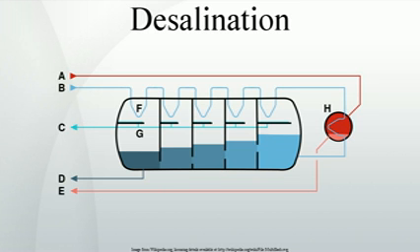Methods. The traditional process used in these operations is vacuum distillation, essentially the boiling of water at less than atmospheric pressure and thus a much lower temperature than normal. This is because the boiling of a liquid occurs when the vapor pressure equals the ambient pressure and vapor pressure increases with temperature. Thus, because of the reduced temperature, low-temperature waste heat from electrical power generation or industrial processes can be used. The principal competing processes use membranes to desalinate, principally applying reverse osmosis technology.